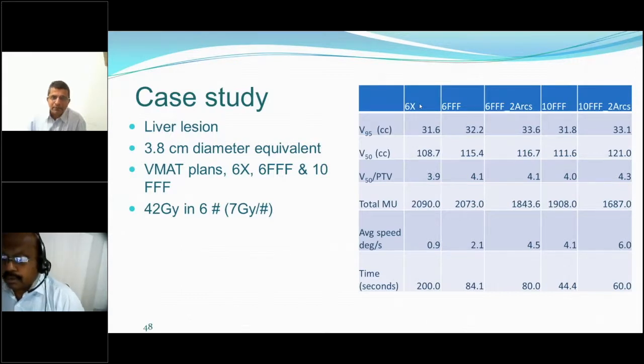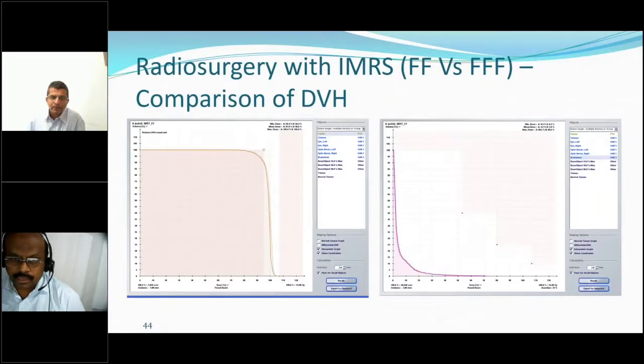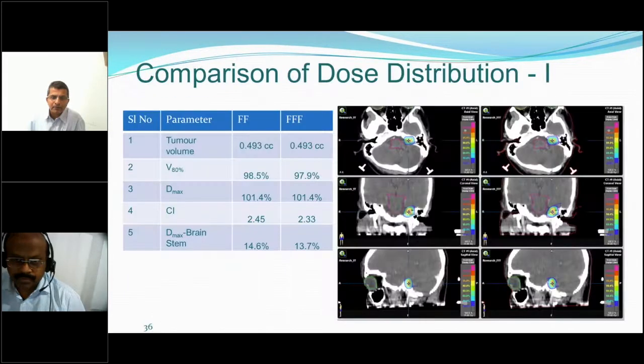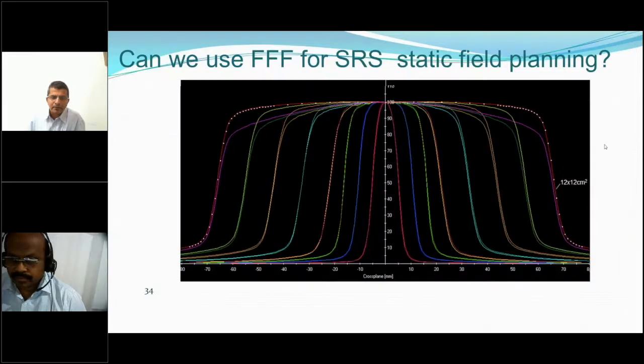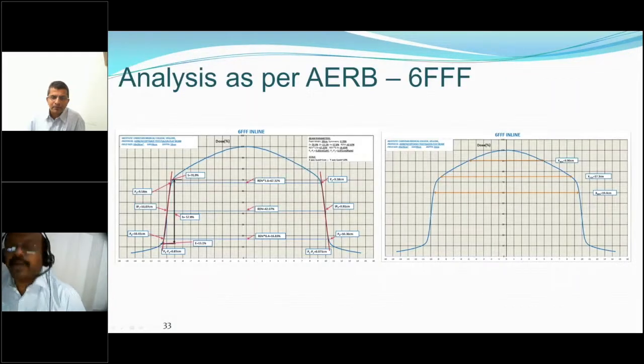Flatness and symmetry, that is totally a different thing. I didn't bring it up in my PowerPoint. There is no flatness. It is an unflattened beam, right? So the degree of unflatness is the one that I spoke about. AERB has a method of measuring the degree of unflatness, whereby they measure the width of the 90%, 75% and 60% profile. So I will show you the degree of unflatness. See, this is where the degree of unflatness is measured. Only AERB wants us to do this, and this is required for our commissioning.